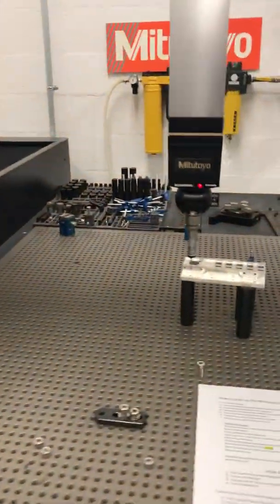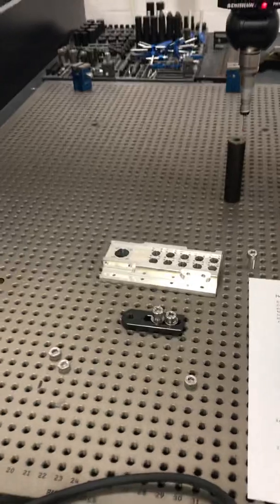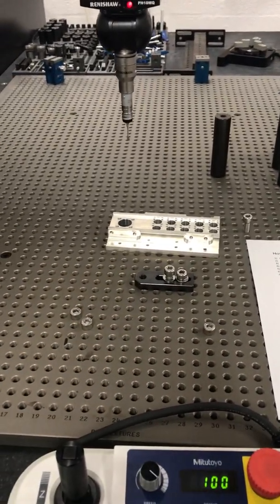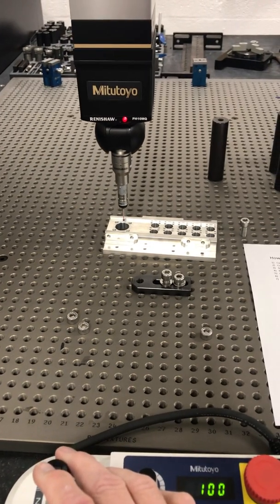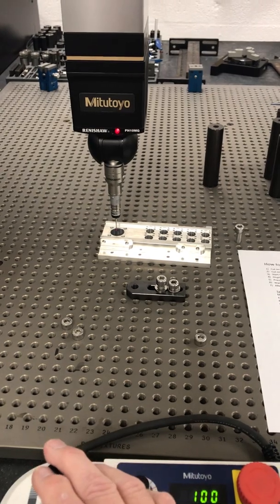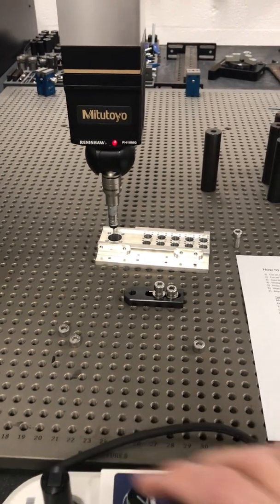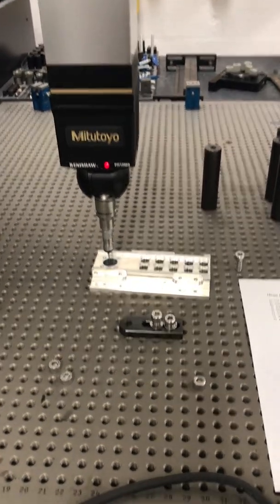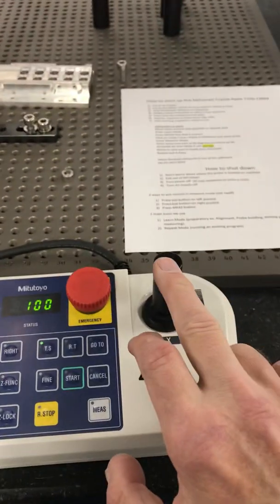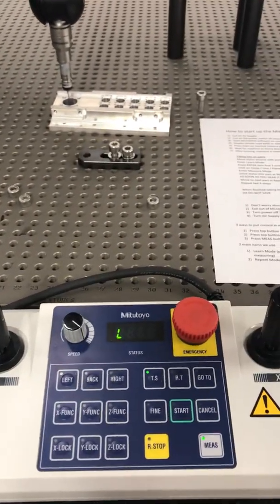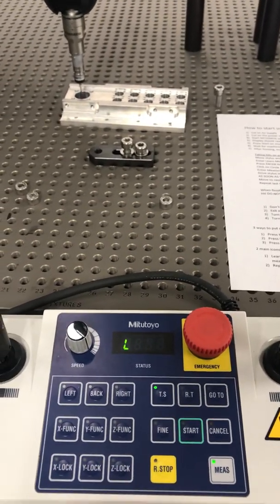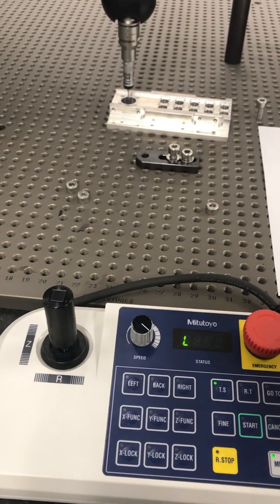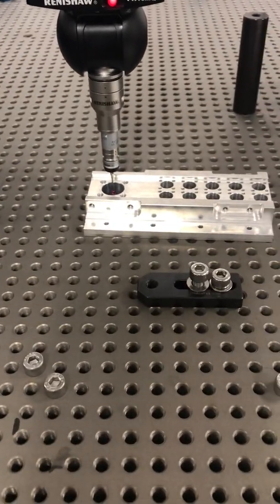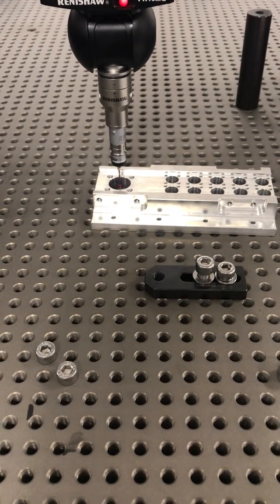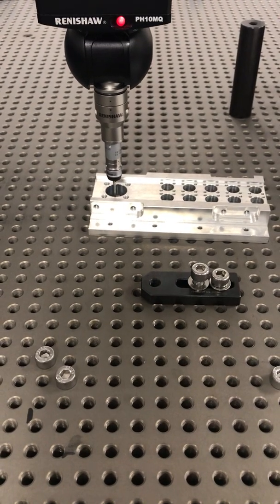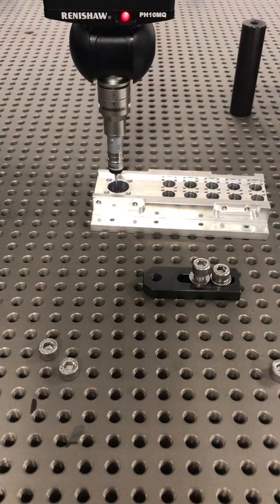So let's go back to here, take this part down, put it right here. Let's drive it. We just want to measure that circle. Let's drop it in. I like to go into the middle, just somewhere randomly down here. Enter measure mode on a joystick. Remember, we can do it here, here, or here. It's got to be an L. Drive the stylus into the part at 90 degrees to wherever you're going. So circles are pretty easy. You can go up. As soon as you hear it, let go. Back. Go back up to the middle and go here.